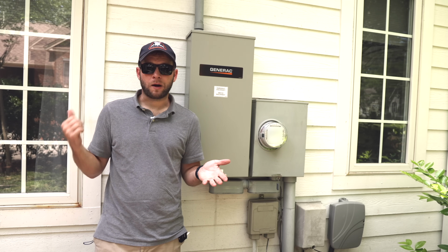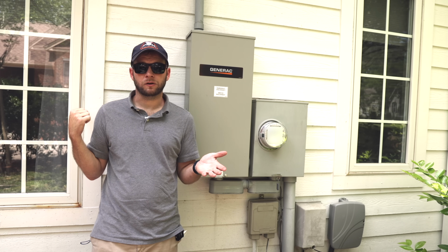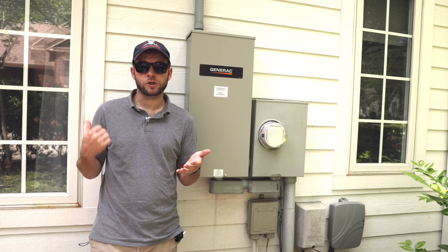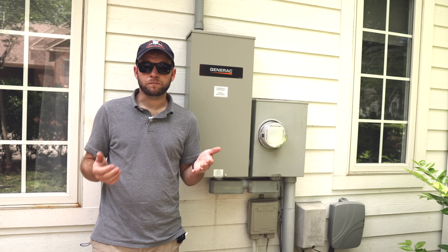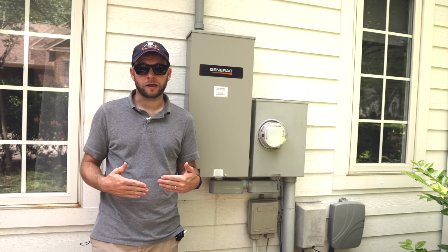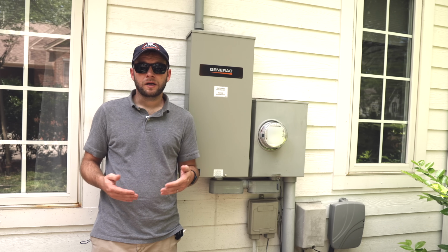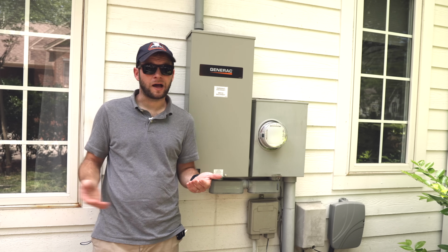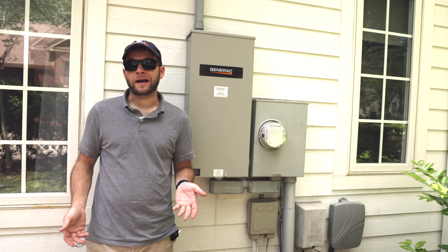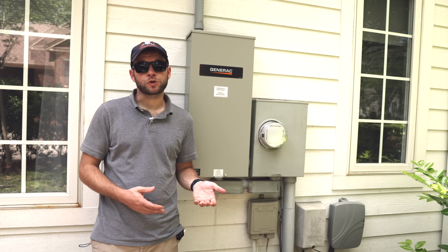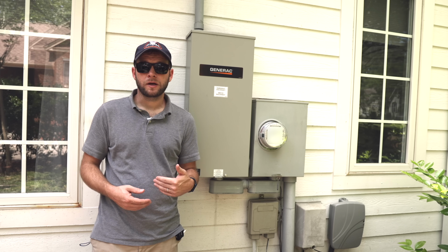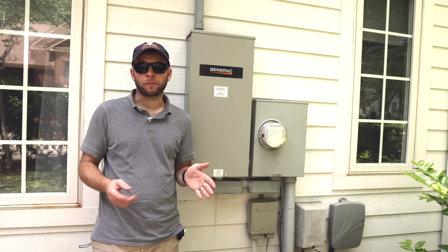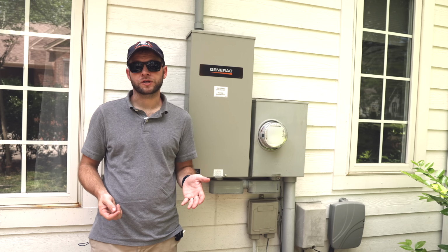So if you've got more power coming from your solar panels than things can handle, it's going to go into the batteries. If the batteries are full, it's going to momentarily shut off the solar panels and pull energy from the battery until the battery is depleted enough that you can then keep charging it. If the solar can't keep up and the battery is draining, it can send a signal to something like one of these to fire up the generator and use the generator to recharge the batteries, all while powering your load. Essentially, the battery acts as a buffer. If you don't have something like a battery, you probably can't use a generator with a solar setup.